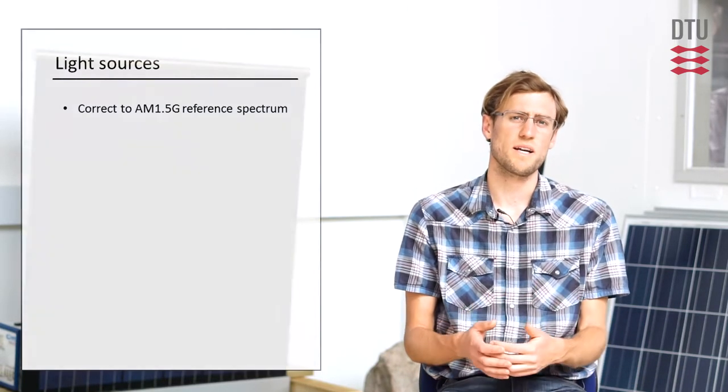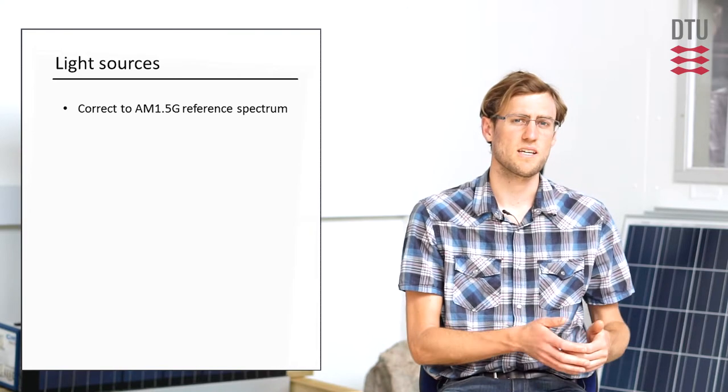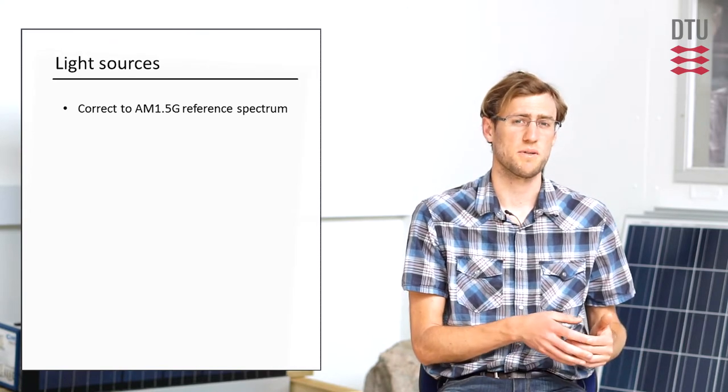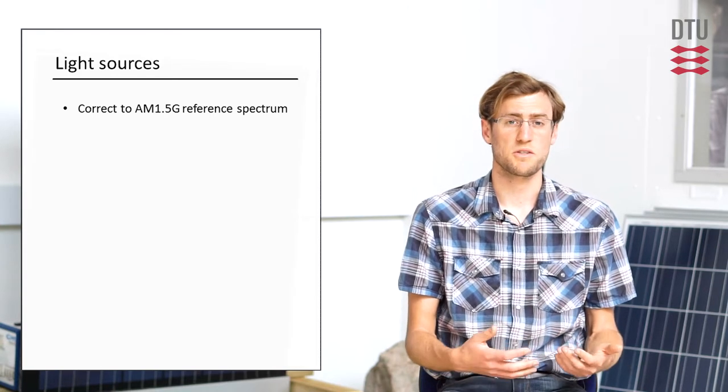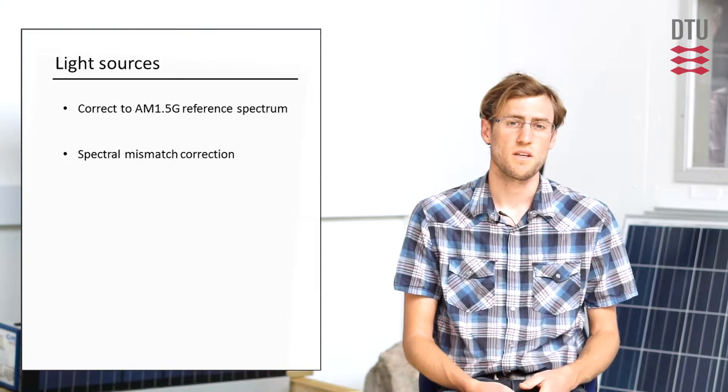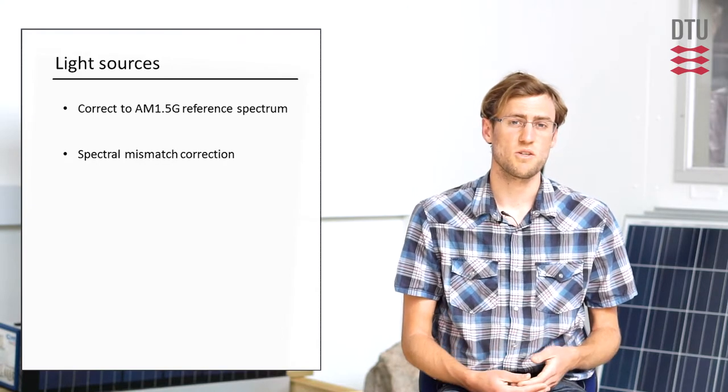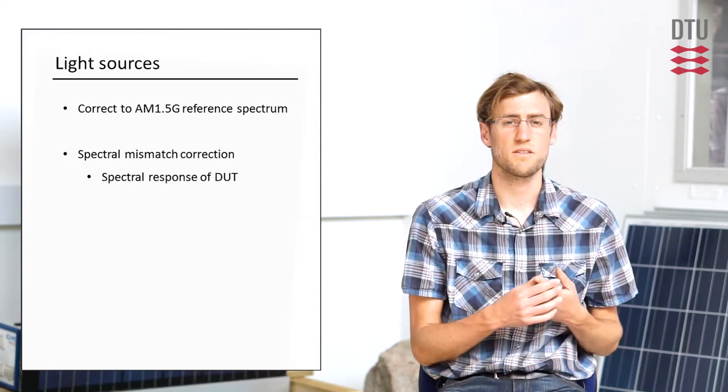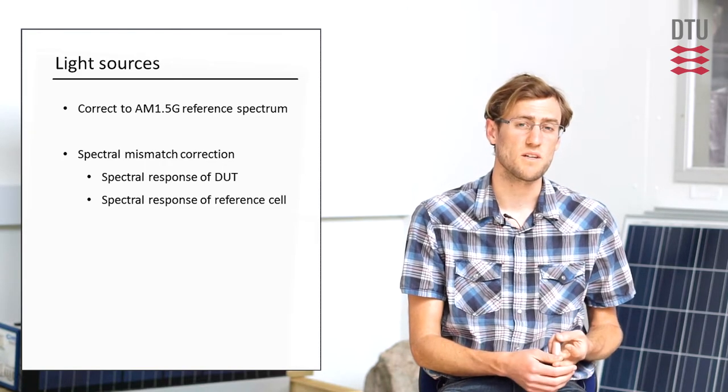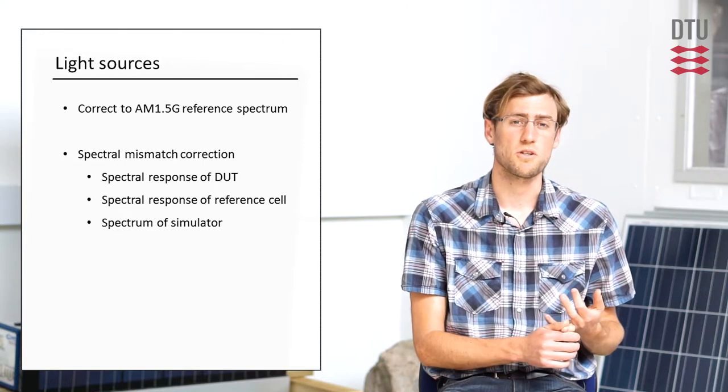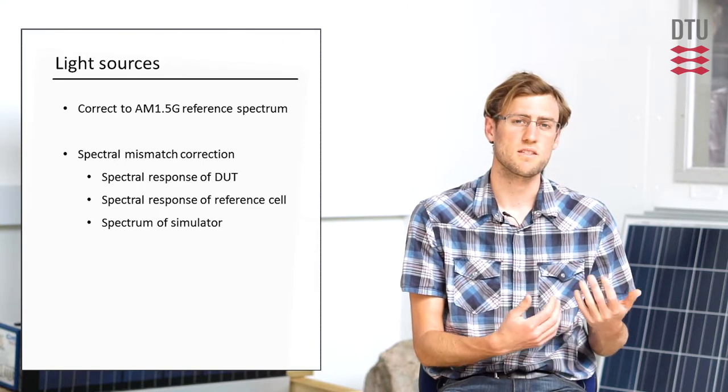Regardless of which light source is used, whether it's xenon, halogen, or even tungsten, it's important to note that we can always correct back to an AM 1.5G reference spectrum if we know a few things. This is called the spectral mismatch correction procedure. We need to know three things: the spectral response of the device under test, the spectral response of the reference cell, and the spectrum of the simulator itself.